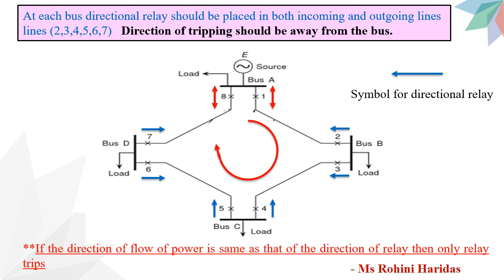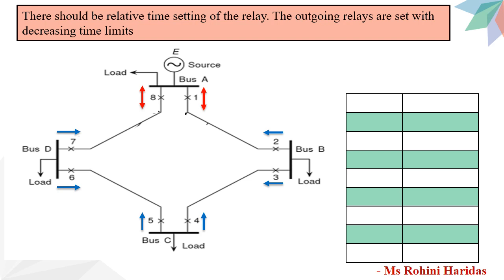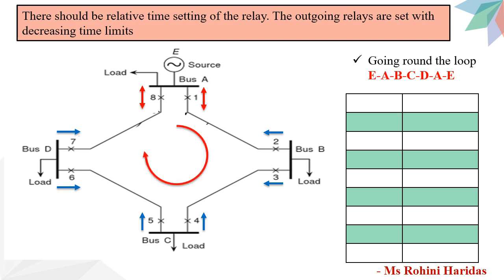If the direction of the power flow is the same as the direction set for the relay, then only the relay trips. Rule number 3 is that there should be a relative time setting of the relays. The outgoing relays are set with decreasing time limits as we go around the loop. Please keep in mind: here we assign time settings to outgoing relays only; for incoming relays, do not assign anything.